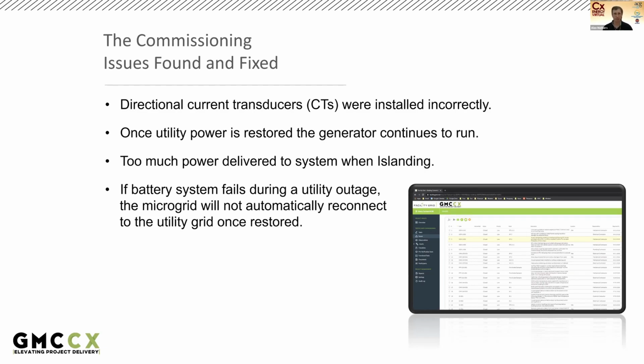The next issue found is that there was too much power in the system when islanding, when there was full sun. The solar inverter curtailing sequence, when in microgrid mode or island mode, was originally set to power up the microgrid with all the solar inverters on at once, and then power them down one by one over time. But there were issues at utility power loss and full solar generation. Voltage was building up on the line, exceeding parameters and tripping the battery. Tesla was then sending the generator start signals since it was tripped.